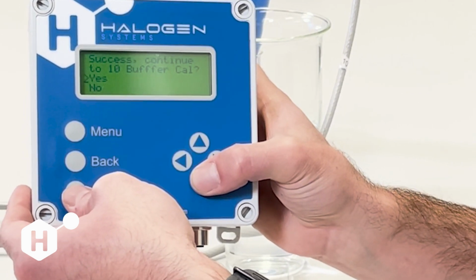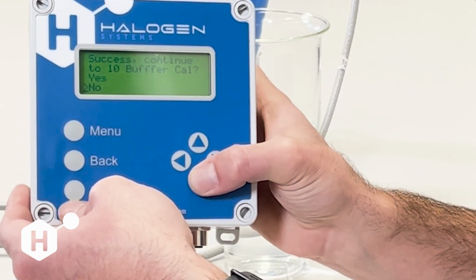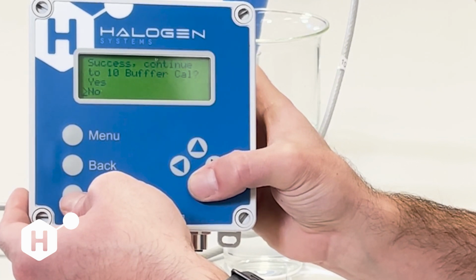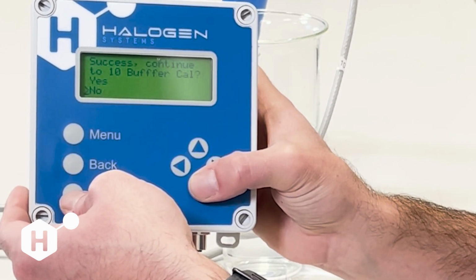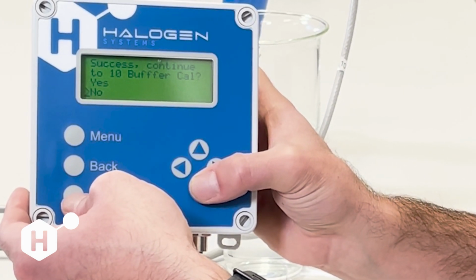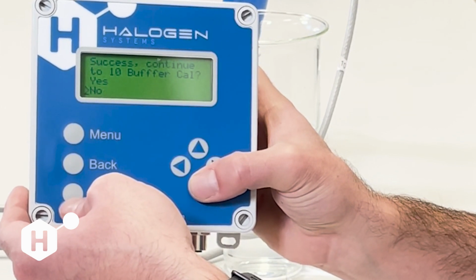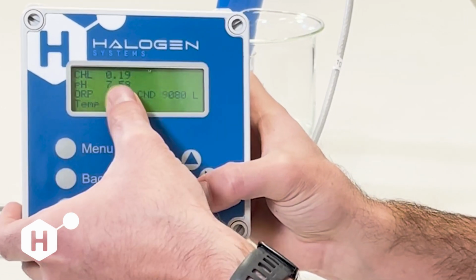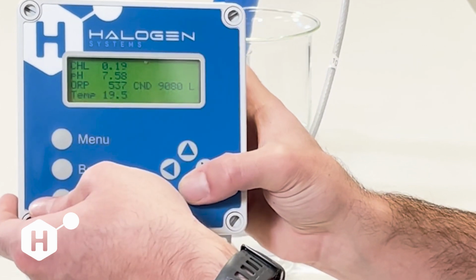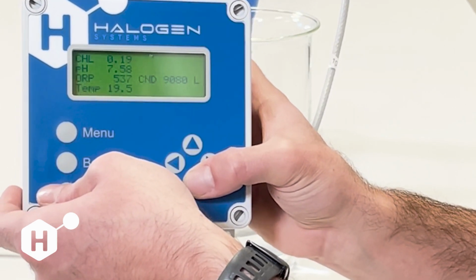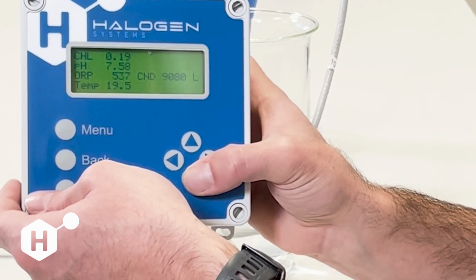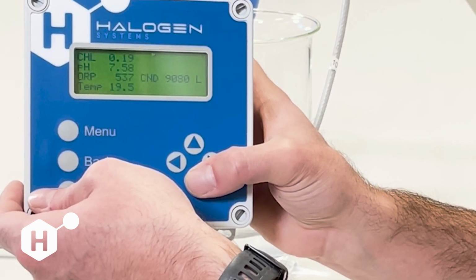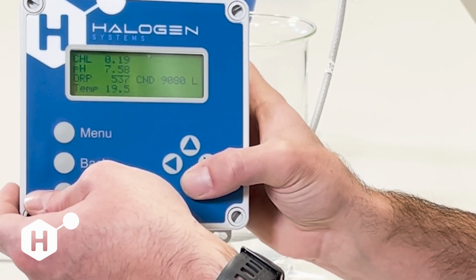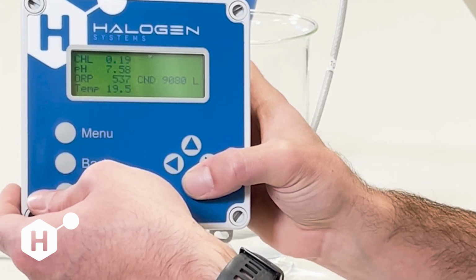buffer cal. In our case, we're going to go ahead and say no, because I want to rinse the sensor, and I want to do the same thing we did with the 7 buffer to confirm that we are stable prior to completing that 10 buffer cal. So I'm going to hit no. That's going to put us back to here. Don't be alarmed that you see a 7.58 here. It usually takes about a cycle for the calibration to update. So we're going to sit here maybe for another minute, and then we're going to confirm that our pH goes to 7.